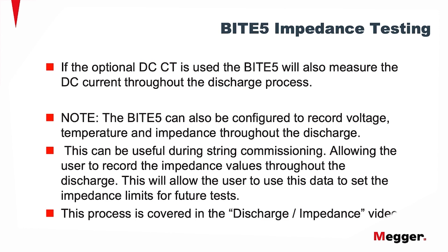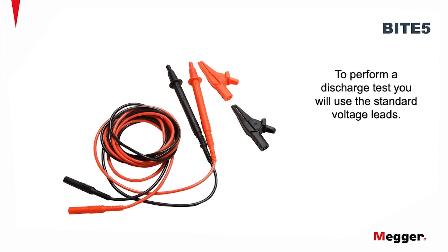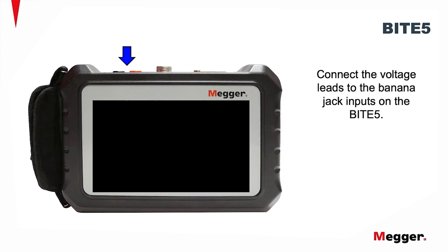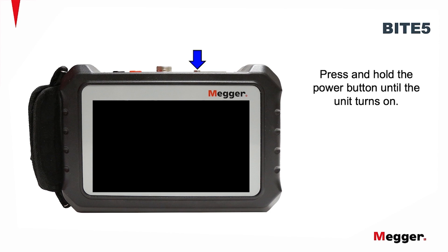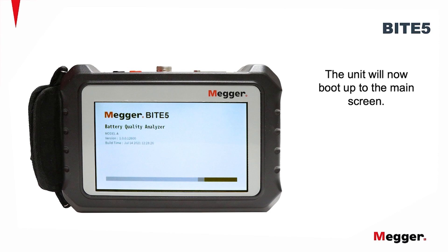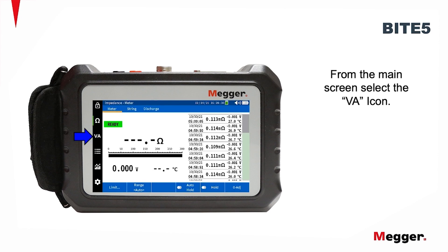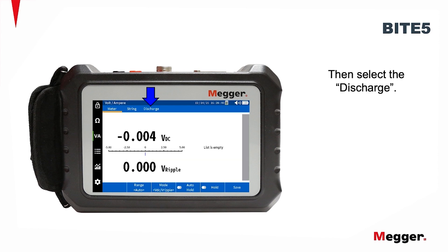This process is covered in the discharge test. To perform a discharge test, you'll use the standard voltage leads. Connect the voltage leads to the banana jack inputs on the BITE5. Press and hold the power button until the unit turns on. The unit will now boot up to the main screen. From the main screen, select the VA icon, then select Discharge.